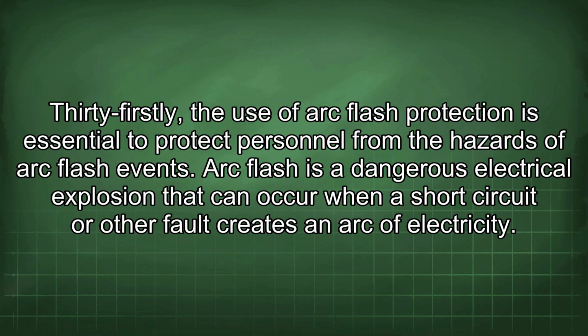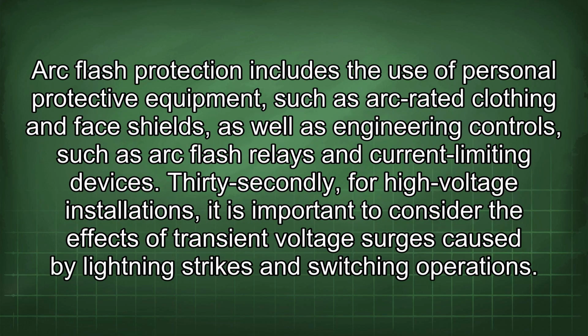31st, the use of arc flash protection is essential to protect personnel from the hazards of arc flash events. Arc flash is a dangerous electrical explosion that can occur when a short circuit or other fault creates an arc of electricity. Arc flash protection includes the use of personal protective equipment, such as arc-rated clothing and face shields, as well as engineering controls, such as arc flash relays and current limiting devices.